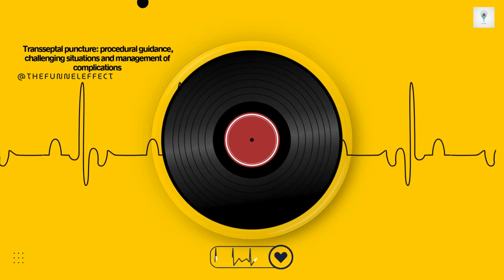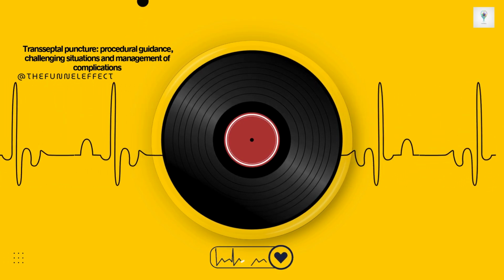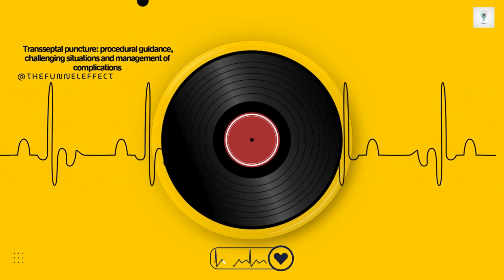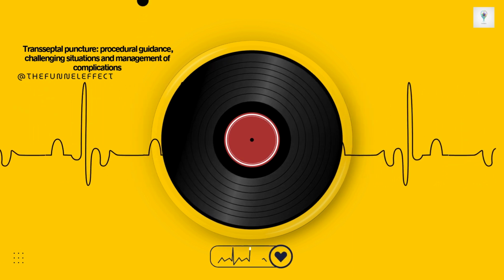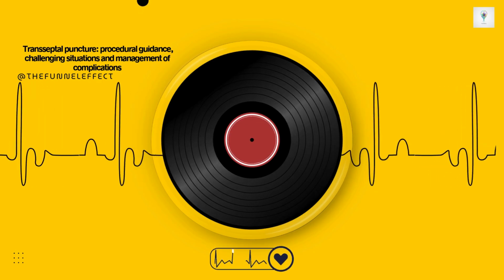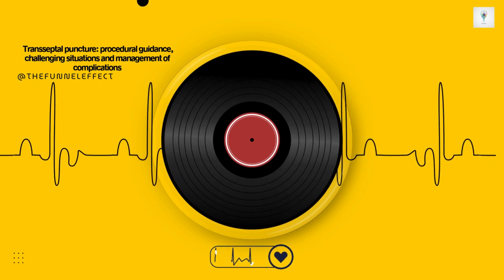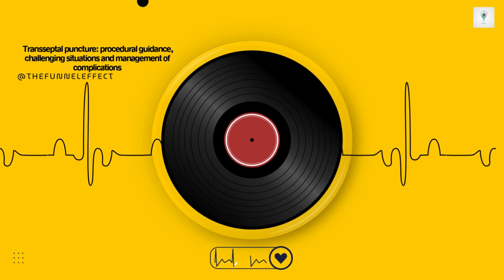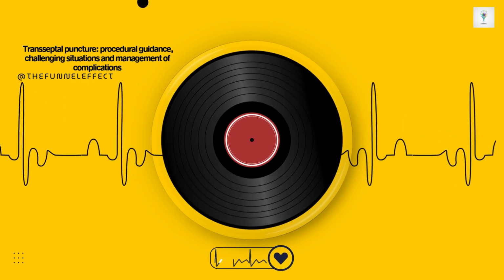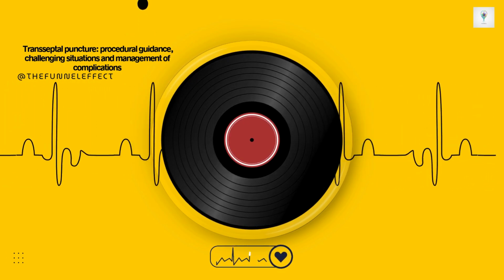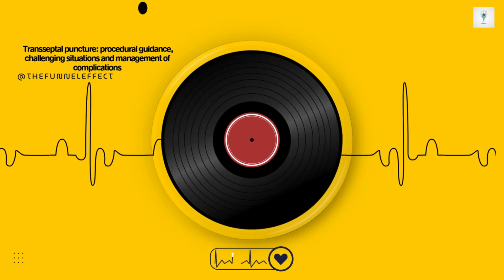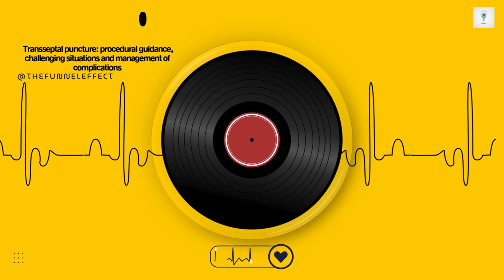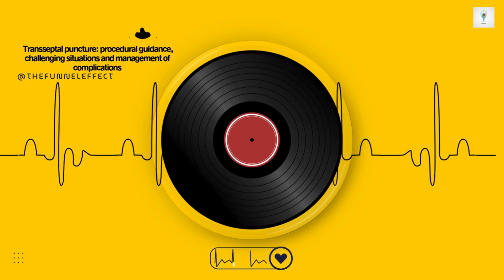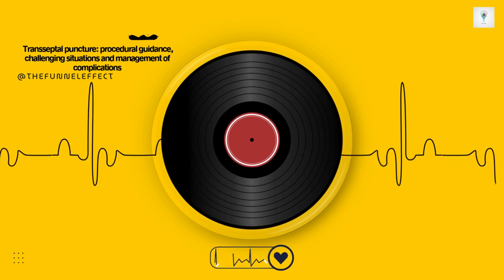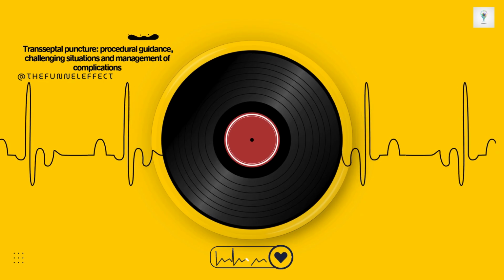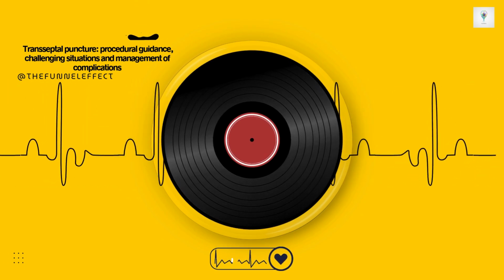Right. Absolutely. One key example is the SafeSept needle-free NF guide wire. This is actually a nitinol wire with a very sharp tip that is designed to create the initial puncture without needing a traditional needle at all. Its crucial safety feature is that once the tip passes through the septum and it loses the support of the surrounding dilator and sheath, its nitinol material properties cause the tip to automatically assume a pre-shaped blunt J curve. This immediately renders the tip incapable of further tissue penetration, effectively stopping any potential overshoot dead in its tracks.